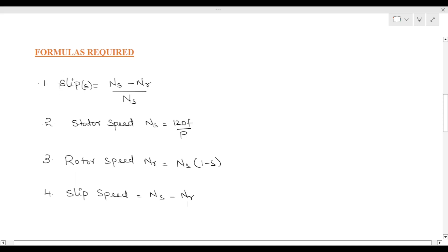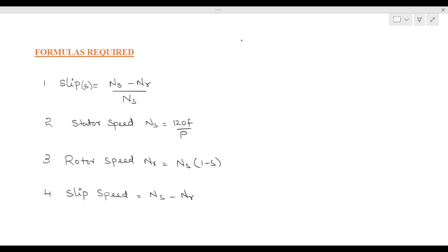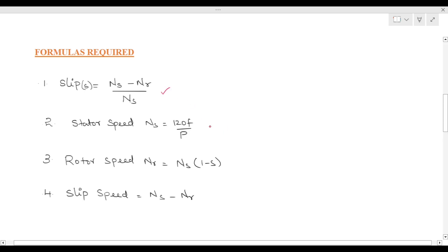Before going to the problems, we need to know what are the different formulas required for solving them. The first formula is: slip s = (Ns - Nr) / Ns. The second formula is synchronous speed Ns = 120f / P. The third formula is Nr = Ns × (1 - s), and the slip speed formula is Ns - Nr.